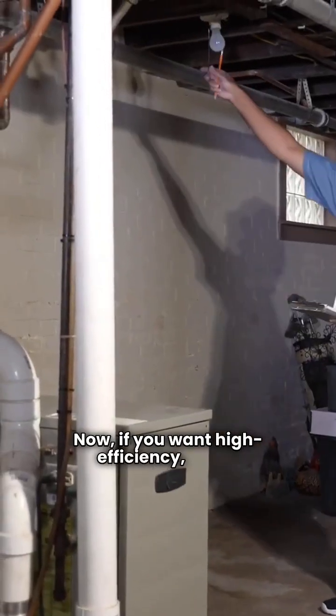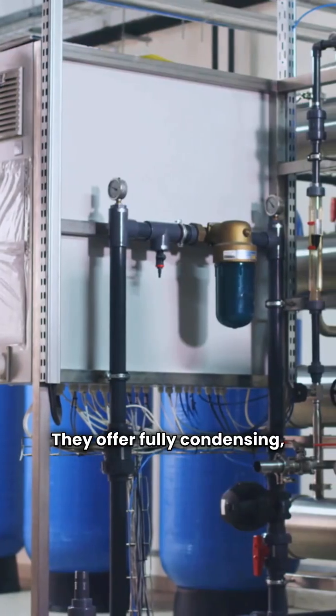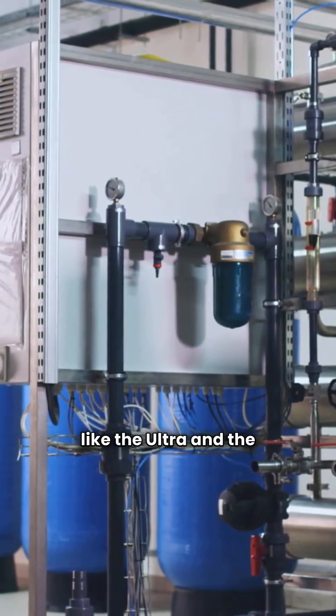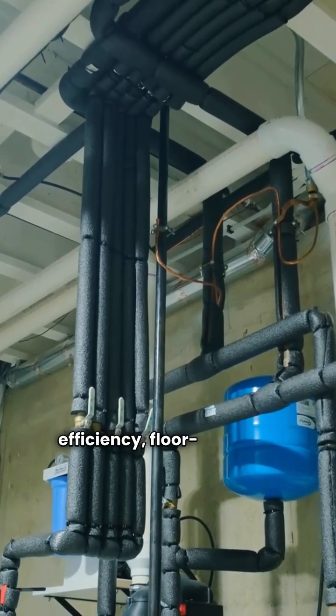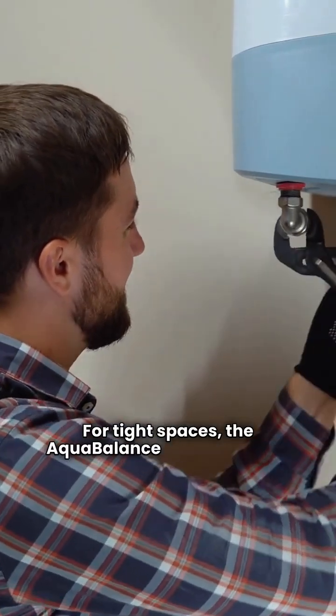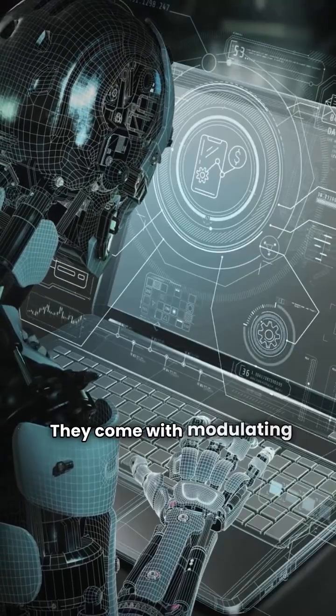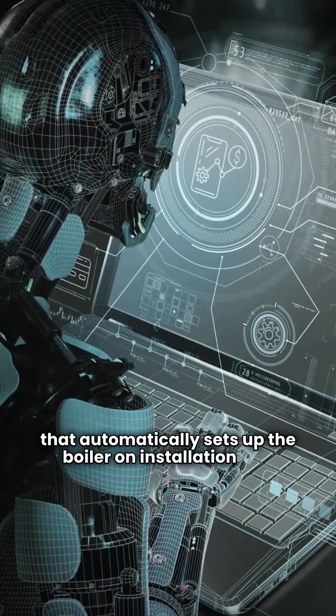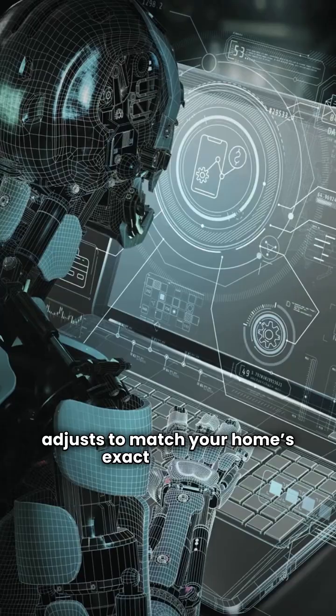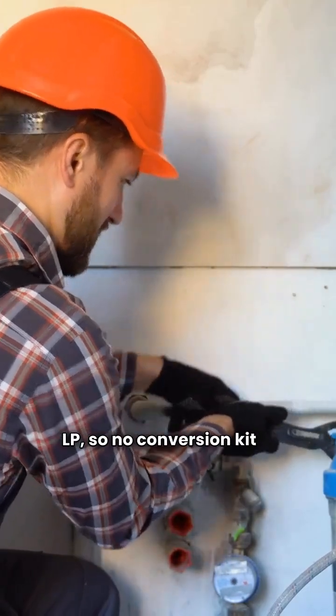Now, if you want high efficiency, that's where Weil-McLain really pulls ahead. They offer fully condensing, modulating units like the Ultra and the Aqua Balance. These boilers can hit a much higher 95% AFUE rating. The Ultra is your high-efficiency floor-standing option. For tight spaces, the Aqua Balance is a wall-hung unit. These aren't just efficient, they're smarter. They come with modulating control and AI control technology that automatically sets up the boiler on installation and adjusts to match your home's exact heat loss. They even automatically adjust for natural gas or LP, so no conversion kit is required.